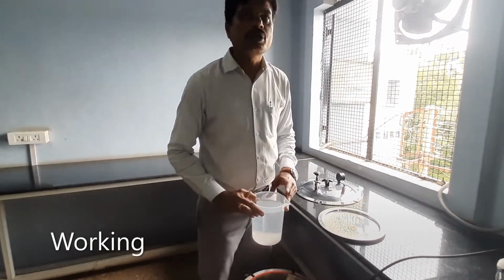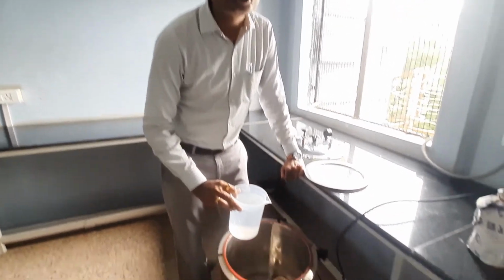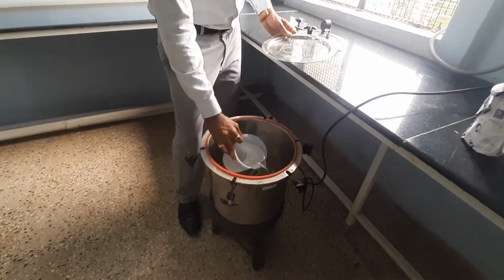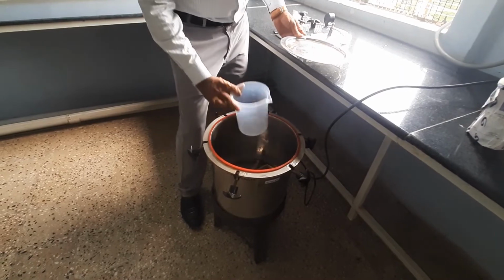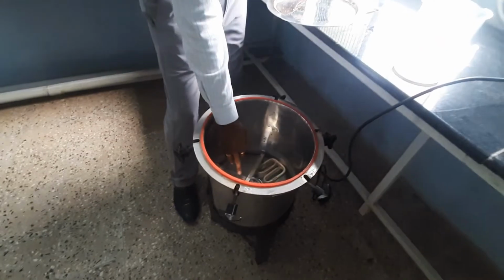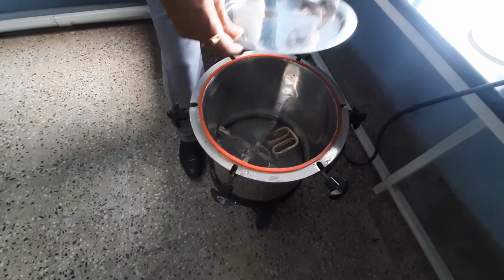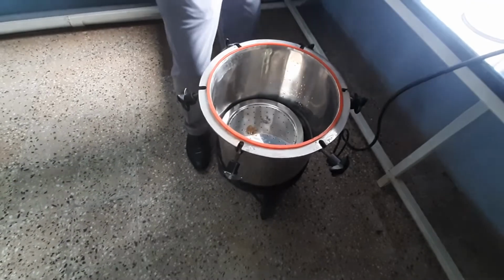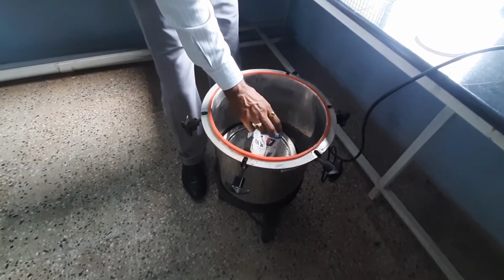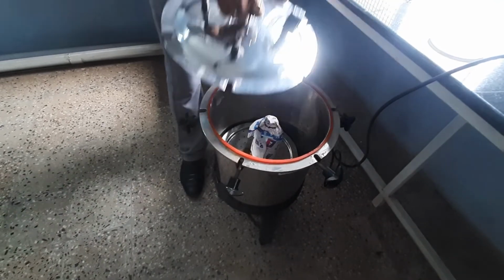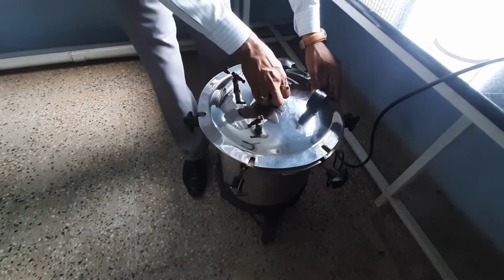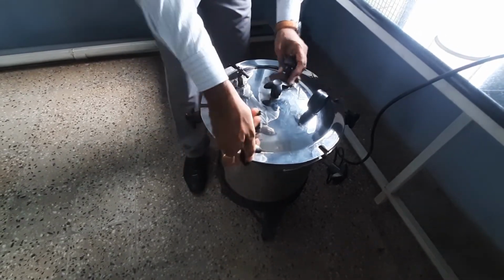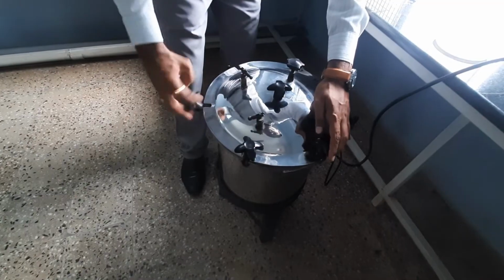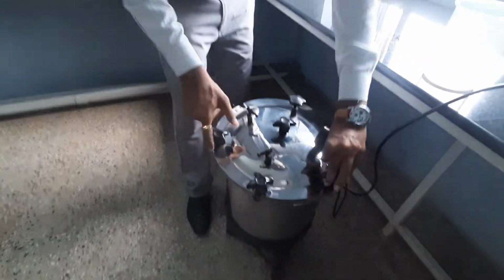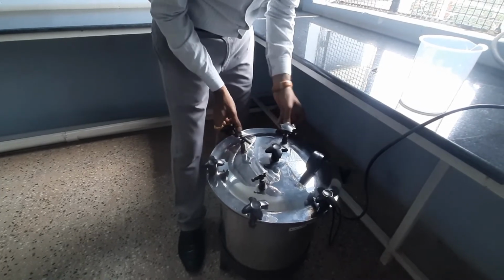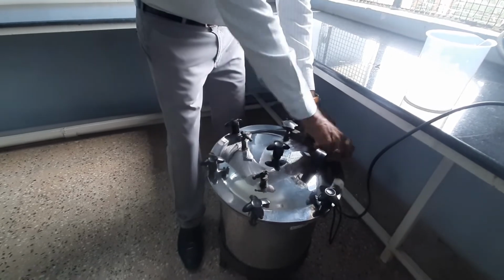Now, here is the working of the autoclave. A sufficient quantity of water is poured into the chamber after removing this perforated basket. The level of water is adjusted in such a way that it should not touch the bottom of the perforated basket. The material is placed in the basket and placed in the autoclave. Then close the lid with wing nut and bolt. Then switch on the heater.